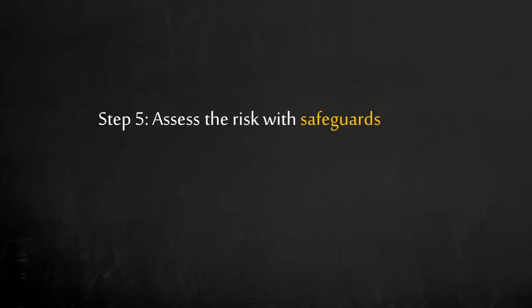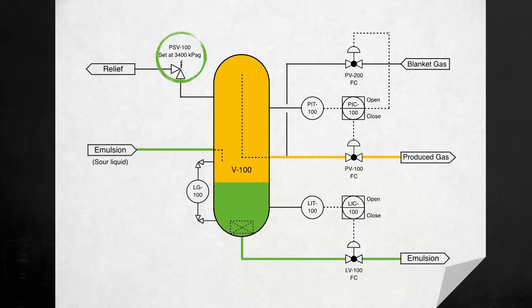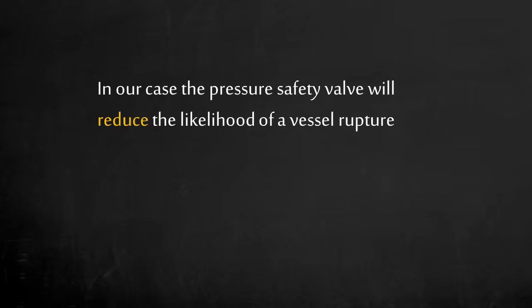Step 5: Now the focus is to reduce the risk by reducing the probability of the consequence. Look for the safeguards and assess the risk with safeguards applied. Is there an alarm with operator intervention? Is there a pressure safety valve on the vessel? Is there an automatic safety shutdown on the high pressure alarm? There is a pressure safety valve PSV-100 designed for this blocked flow case. The pressure safety valve will reduce the likelihood of a vessel rupture, but this will not eliminate the risk since the pressure safety valve can potentially fail.